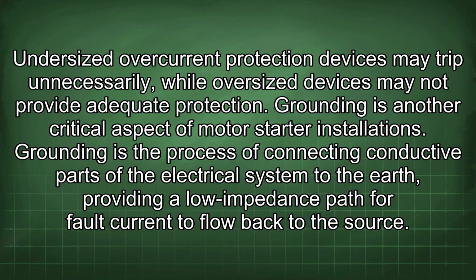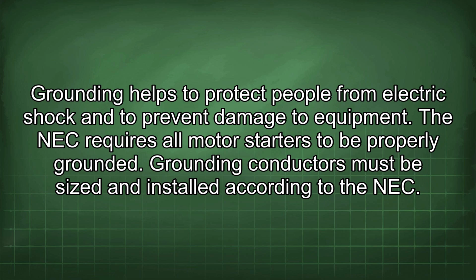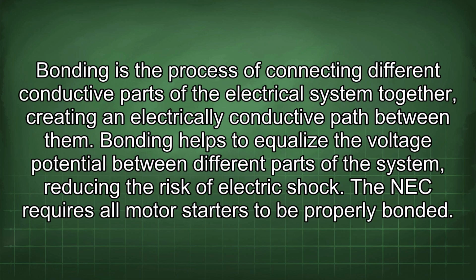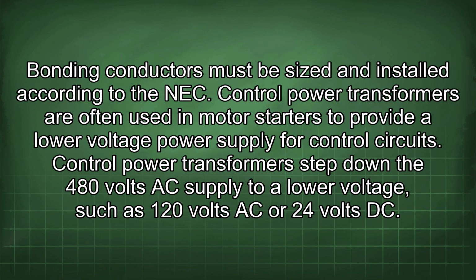Grounding is another critical aspect of motor starter installations. Grounding is the process of connecting conductive parts of the electrical system to the earth, providing a low impedance path for fault current to flow back to the source. Grounding helps to protect people from electric shock and to prevent damage to equipment. The NEC requires all motor starters to be properly grounded. Grounding conductors must be sized and installed according to the NEC. Bonding is the process of connecting different conductive parts of the electrical system together, creating an electrically conductive path between them. Bonding helps to equalize the voltage potential between different parts of the system, reducing the risk of electric shock. The NEC requires all motor starters to be properly bonded. Bonding conductors must be sized and installed according to the NEC.